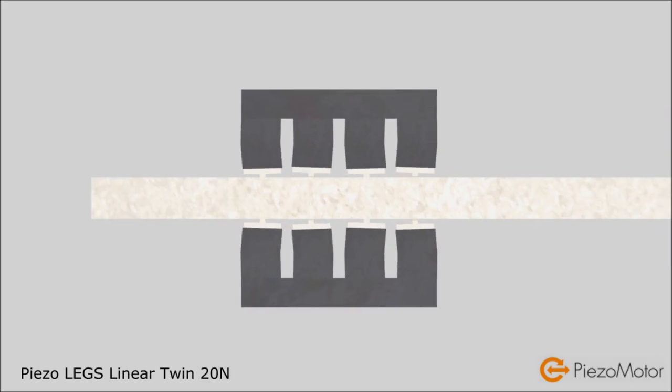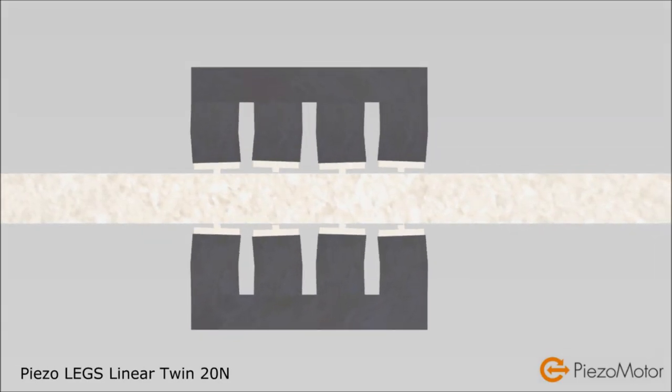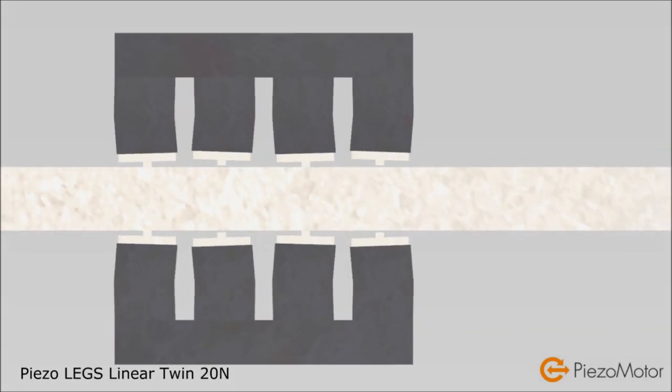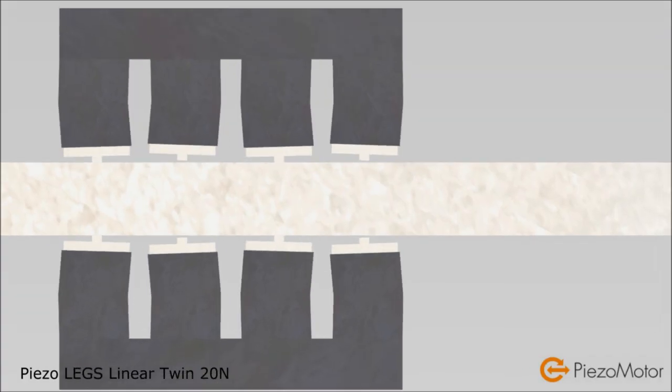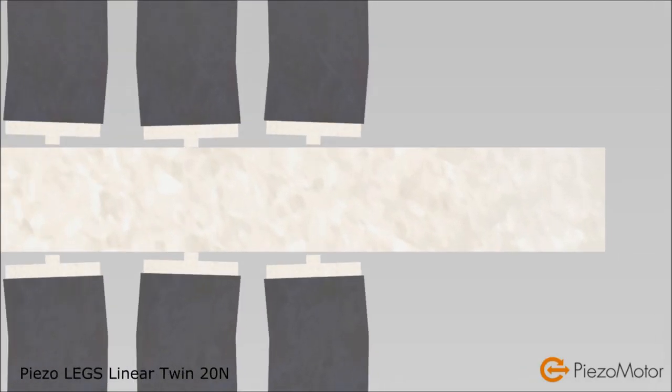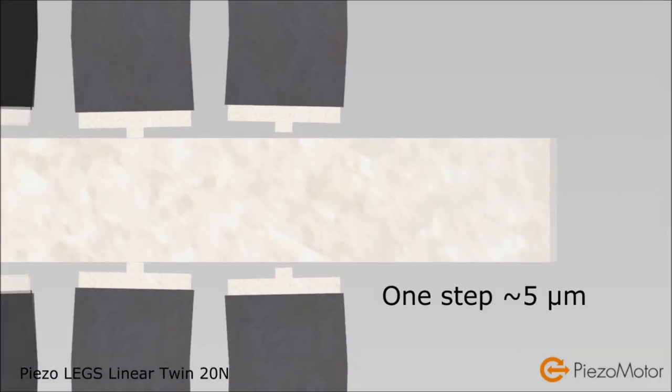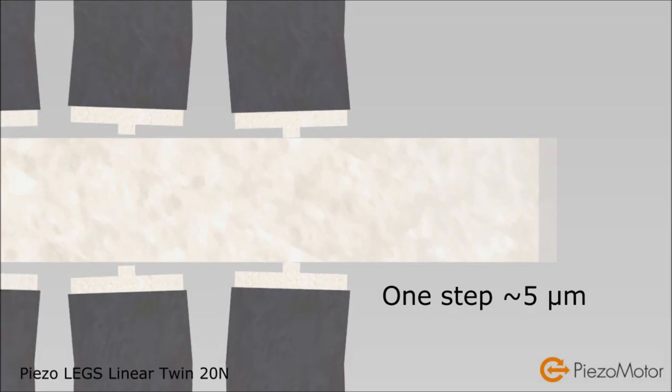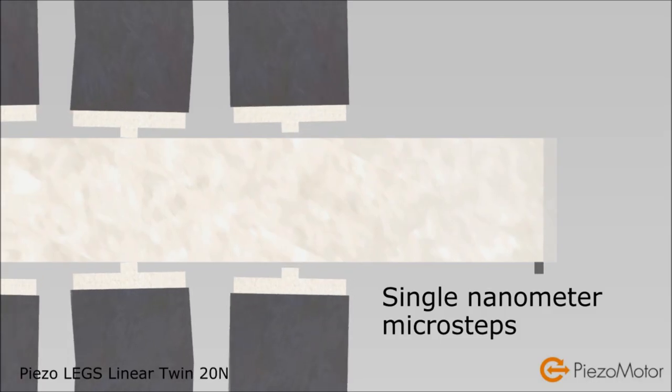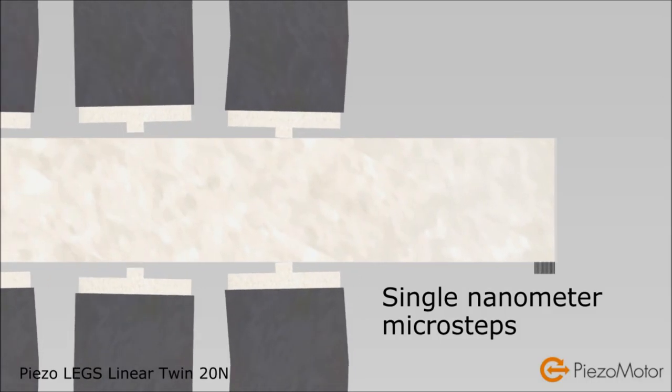Speed is variable by selecting the frequency of the electrical waveform. One single period will move the drive rod by a few microns. The full waveform step can be divided into thousands of microsteps. Each microstep is in the single nanometer range.